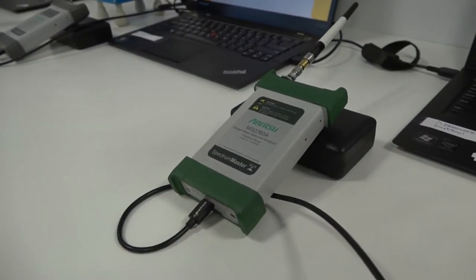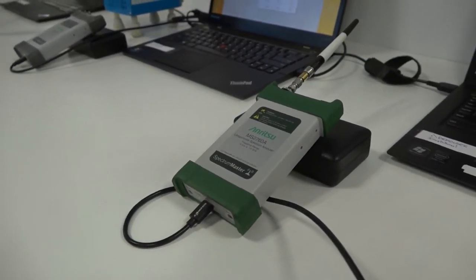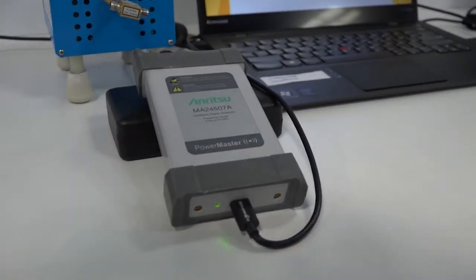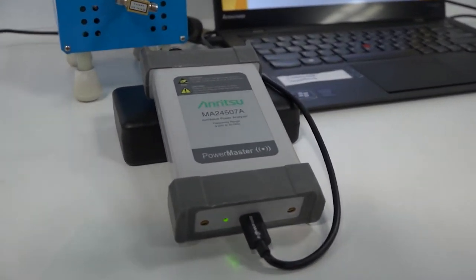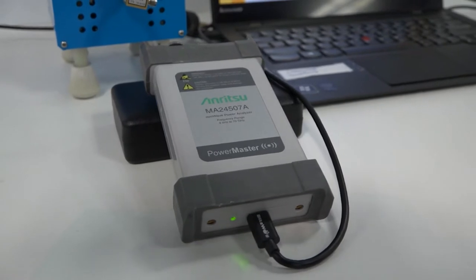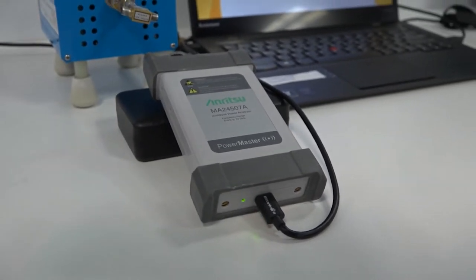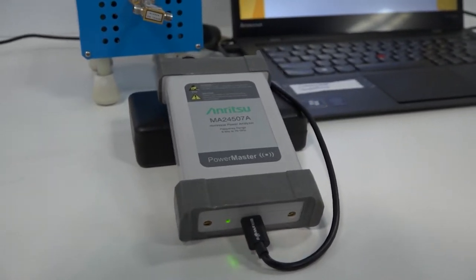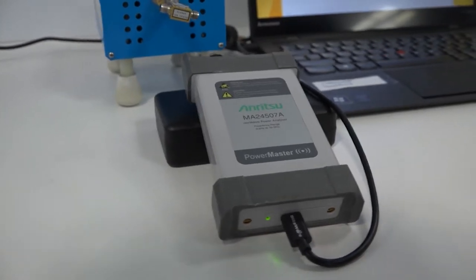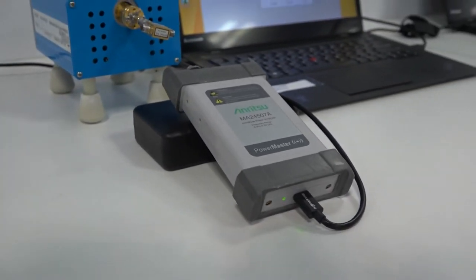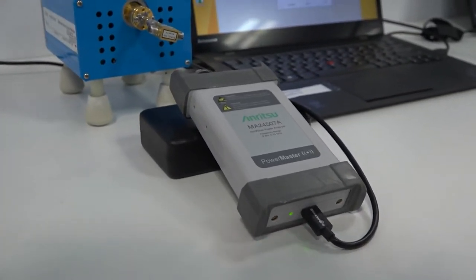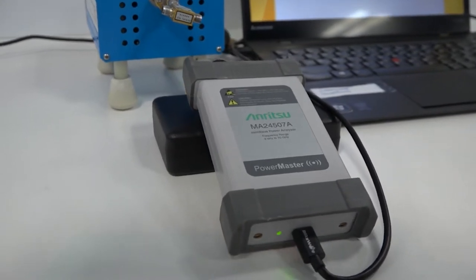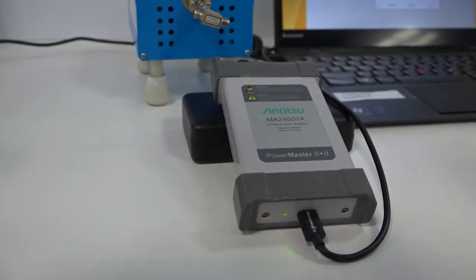In addition to the Spectrum Analyzer, we're also showing a new product called a PowerMaster. And this is a unique product because it's in between a traditional power sensor and a Spectrum Analyzer. With a traditional power meter, those are very broadband devices. They measure anything in the broadband spectrum that it's measuring.